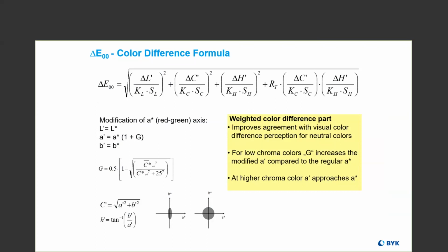So there is no numerical conversion. There's no way to convert LAB values taken with a 45-0 instrument to LAB values taken with a sphere instrument. You just have to choose the correct spectrophotometer for your application, whether you want to measure color as you see it with gloss included, or you want to just measure the pigmentation exclusive of the gloss or surface texture.